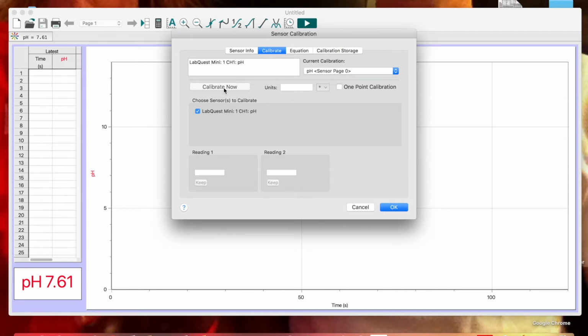So we're going to click Calibrate now, and we're going to wait until this reading here stabilizes. Now remember, we talked about how this pH probe essentially is measuring a voltage difference between the standard solution it has inside the stalk of it and then the relative H+ concentration outside. It works on the principle of what's called a concentration cell, which we don't need to get into now. Suffice to say, the higher the voltage is here, the larger the difference between the H+ concentration inside the probe and outside is.